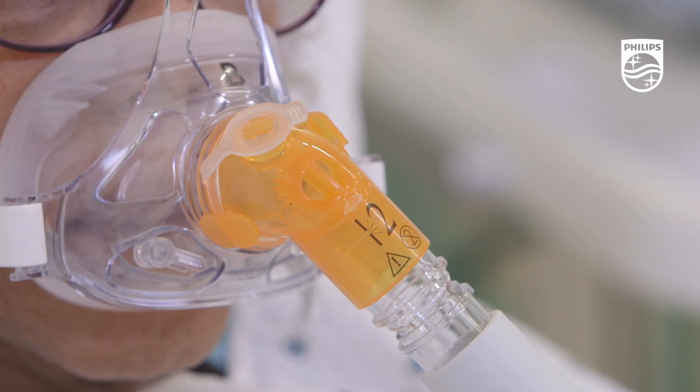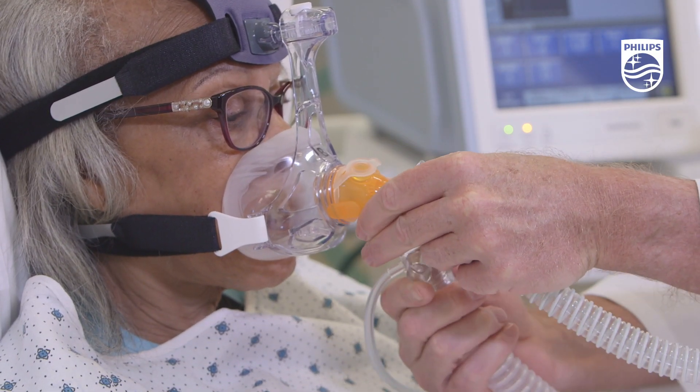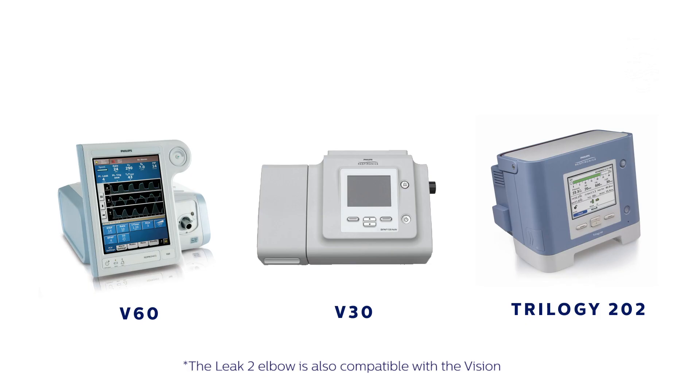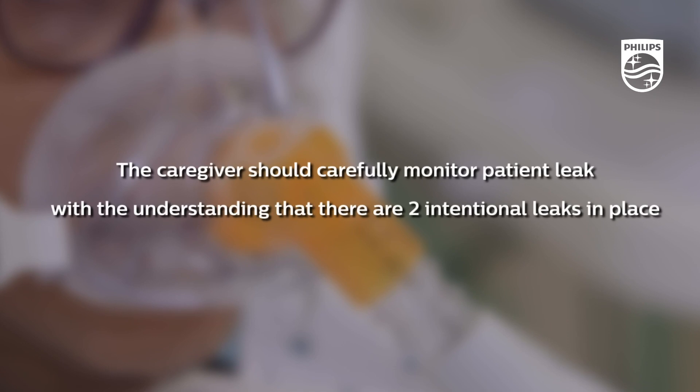The Leak 2 elbow has a leak port built in and is designed for use with either the dedicated BiPAP circuit or straight tube used for home care applications. With the Leak 2 elbow, use of the Disposable Exhalation Port is acceptable with the V60, V30, Vision, or Trilogy ventilators, and the intentional leak will be cumulative but within the leak compensation range of these devices. When using a Leak 2 elbow with the DEP circuit, the caregiver should carefully monitor patient leak, as there are two intentional leaks in place.